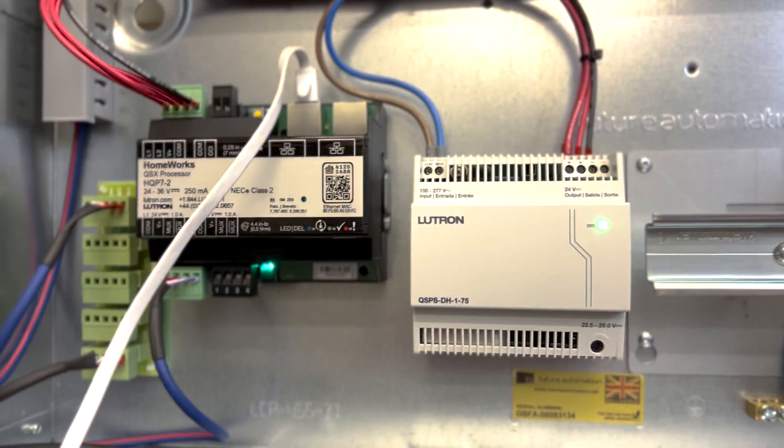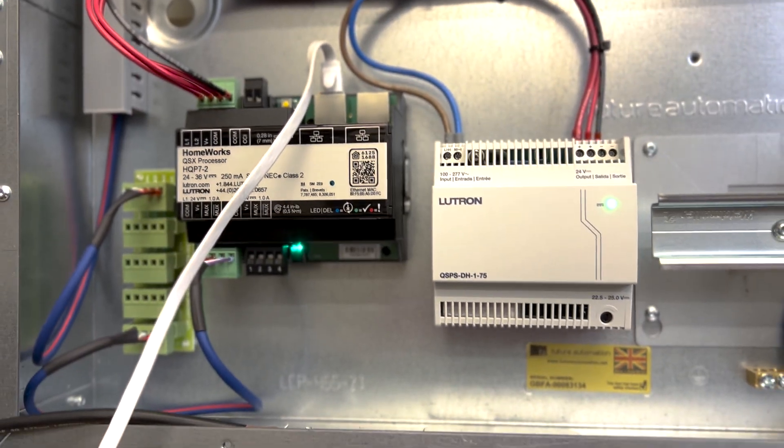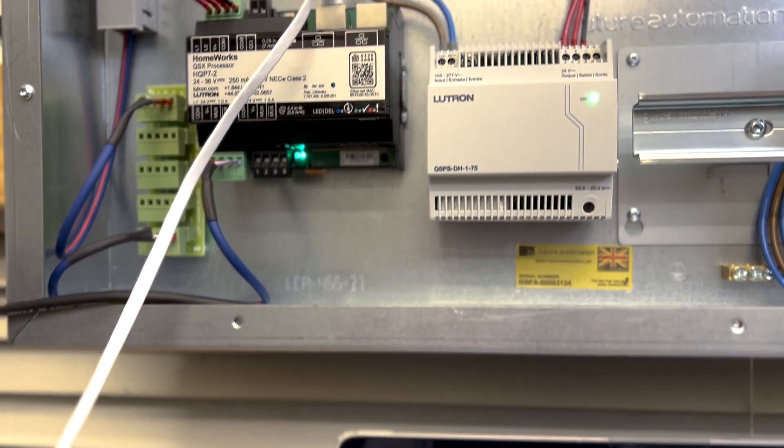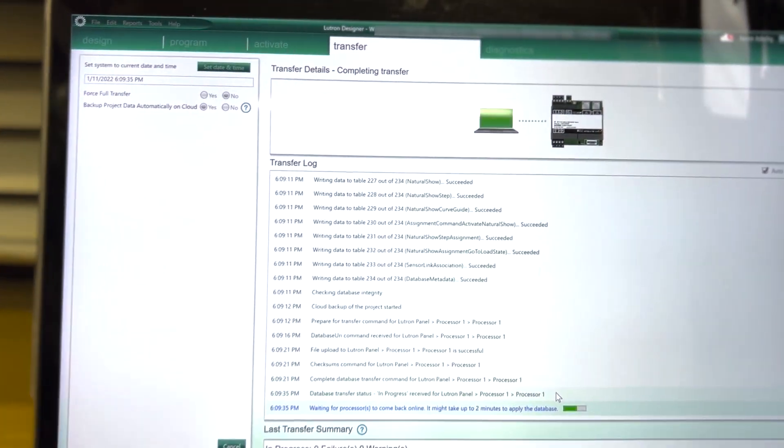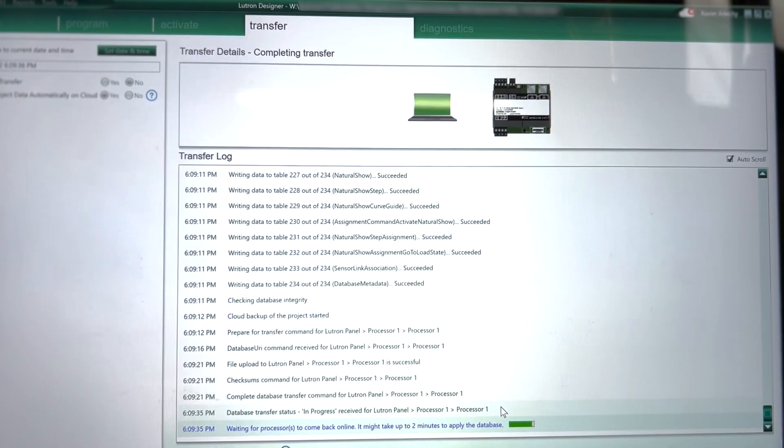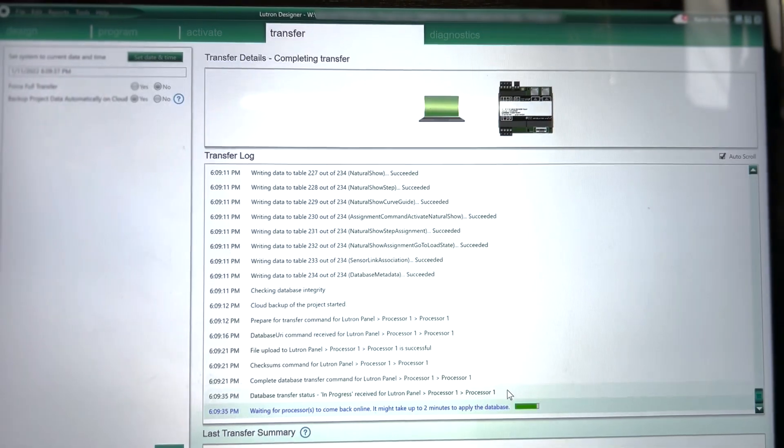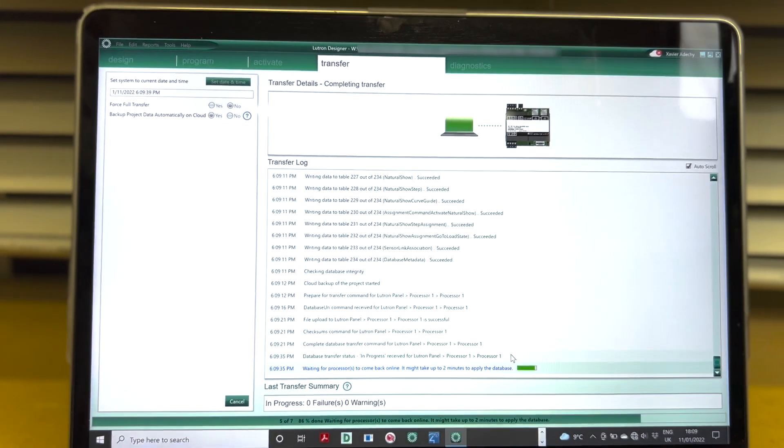I found those ghost-wired future automation panels, to be a very good option for Lutron dealers like myself. All the internal wiring has been beautifully completed, and tested by a well-known, reputable company. Using those ghost-wired panels for a while, I felt more in control in my panel building process. I even uploaded my Homeworks database to the processor, and addressed all my Lutron modules, before delivering the panel to site. Which saved a bit of time, and allowed me to double-check that I had good communication between the modules.